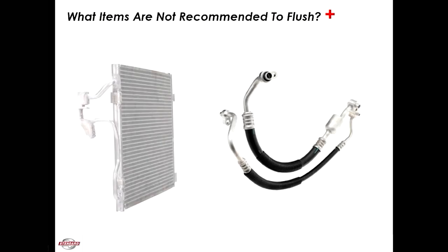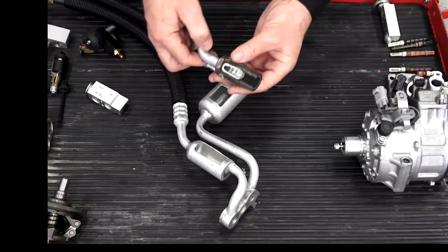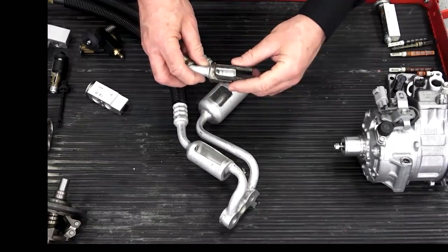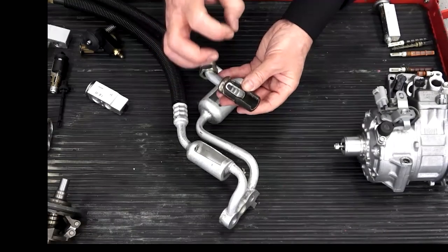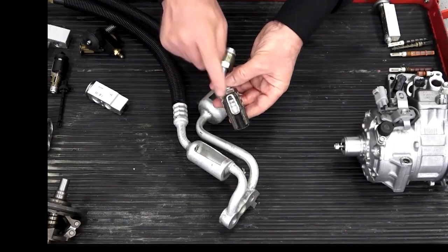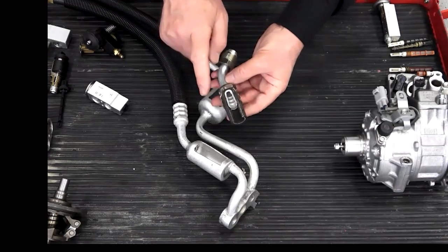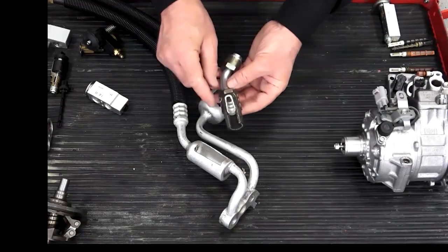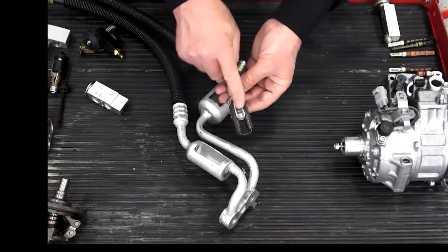A couple of quick things. First of all, rubber hoses, the base compound is rubber. It's organic. It came out of the side of a tree. It's been heat cycled. The truck is 8, 9, 10 years old. The rubber's been heat cycled 10,000 times. Here's a crimp joint here. It's been crimped for the past 10 years. The rubber hardens, shrinks, crystallizes. And so the micro leak that led to the low charge, oil dropout, compressor seizure is very often, I would say, the primary cause of original compressor failures: micro leaks from hose crimps.